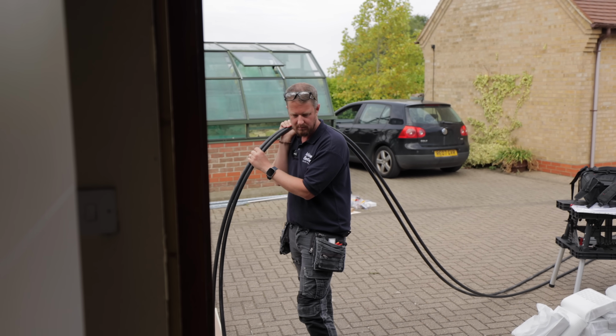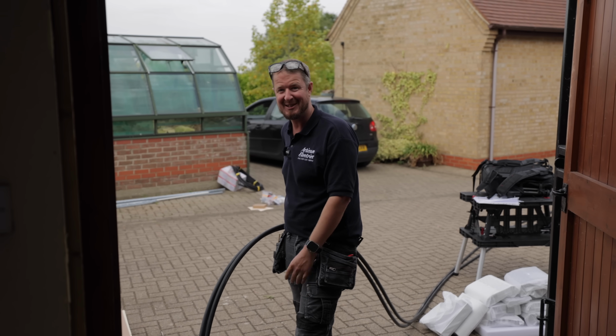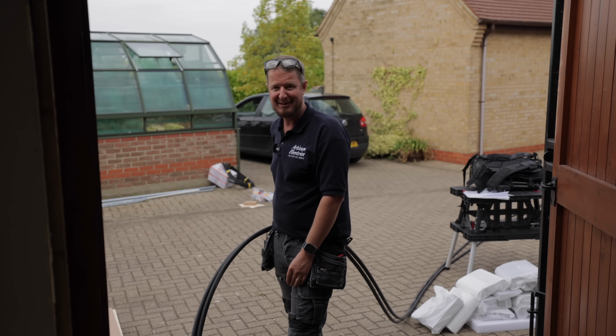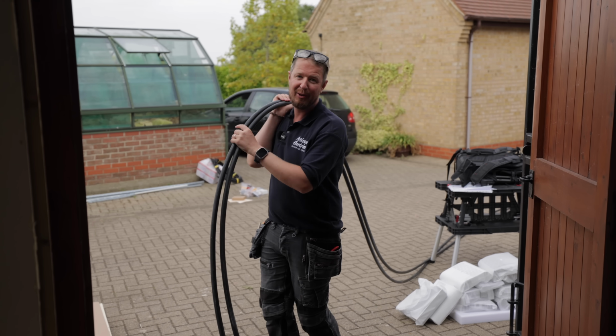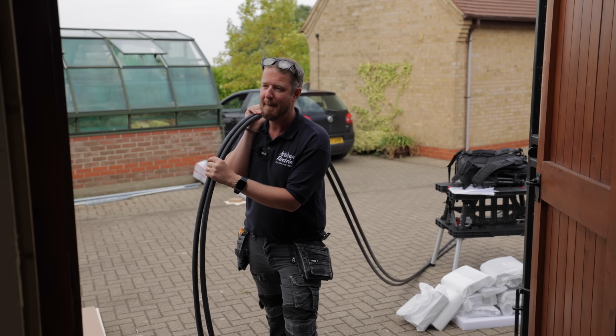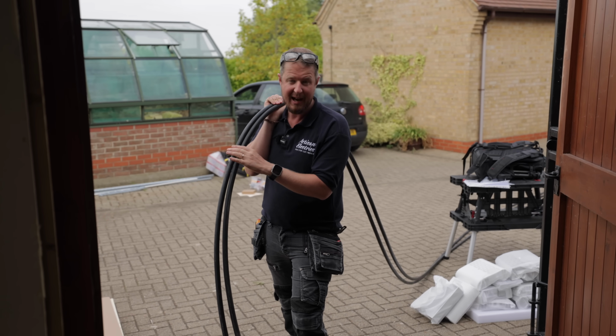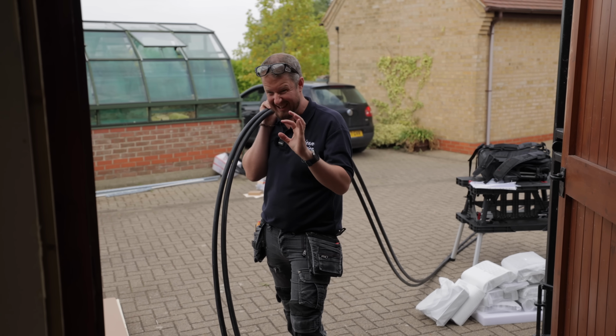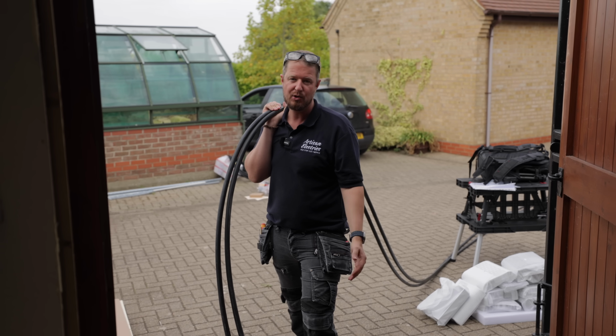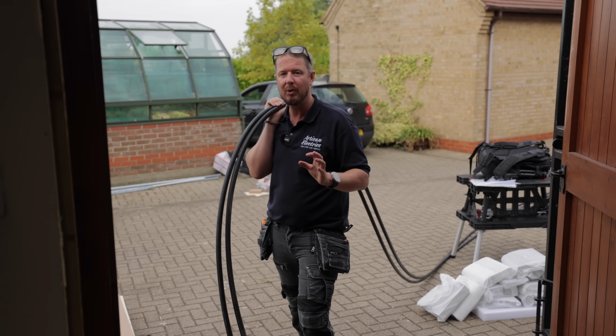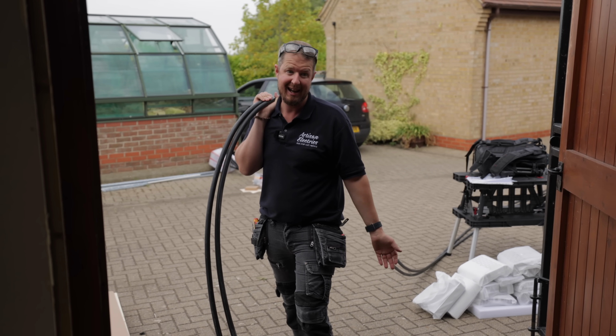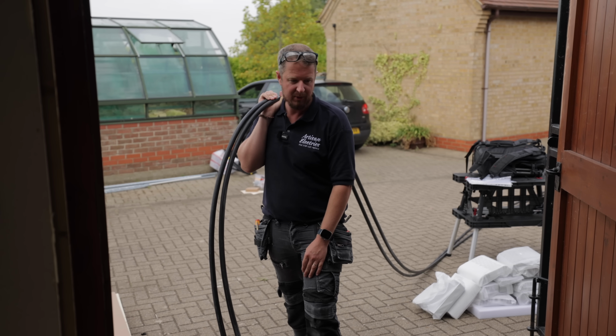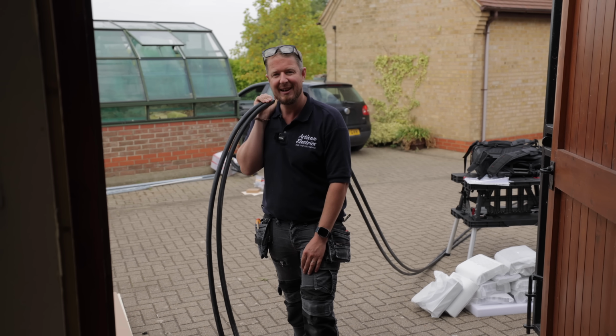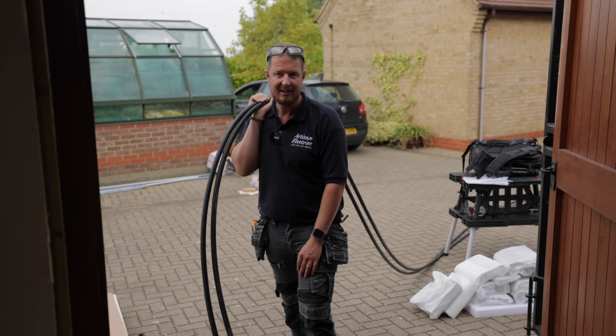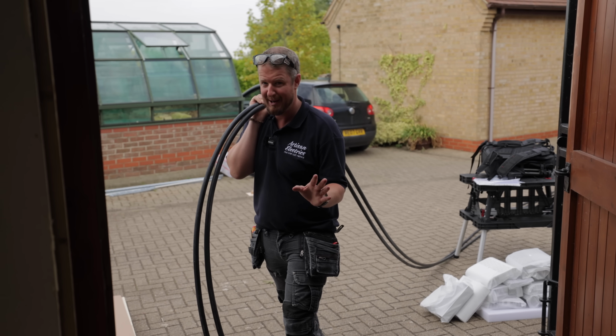I know this cable looks really long for the run, but somebody once told me that the most expensive cable is the one that's 10 centimeters too short, and that's a lesson I've learned the hard way a few times in life. My uncle used to work for my dad, and he was a little economical, shall we say, so he'd never want any wastage and would always cut cables exactly to the length needed. But then if you had to change anything or pull something slightly, it was always too short, and it ended up costing more because you'd have to pull in a whole new cable. So my motto now is it's okay to have a couple of meters extra slack if needed, just to give you a little wiggle room. Always overestimate your cable runs.